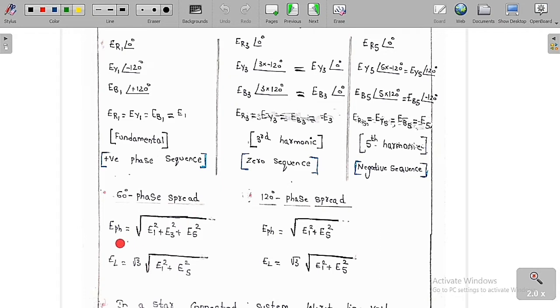Then what is the EMF induced per phase? EMF induced per phase is equal to under root over E1 square plus E3 square plus E5 square. Then line voltage is equal to root 3 times the phase voltage. So root 3 times of under root over E1 square plus E5 square. Therefore simply we can say that in the line voltage there will be no third harmonic components, only fundamental and fifth harmonics are going to be present, but not the third harmonic component. This is a very important point that you always have to remember. So we can simply say that in the phase voltage we have third harmonic component, but in the line voltage there will be no third harmonic component.